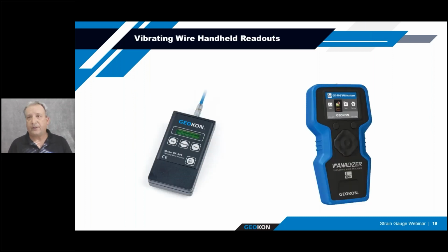To do pre-installation testing and the installation correctly, it's a good idea to have handheld readouts. We offer a couple in-house. The GK404 on the left is a simple vibrating wire readout that provides output in digits, either frequency-based in hertz or microstrain, typically used for strain gauges. It doesn't save any data; it's basically a readout device that tells you what it's reading, so you'd jot the information down in a field notebook.